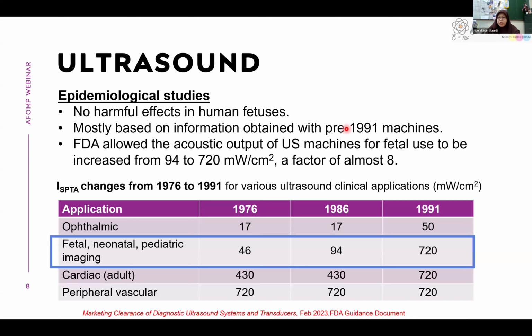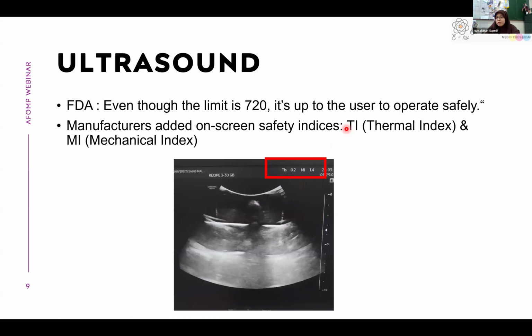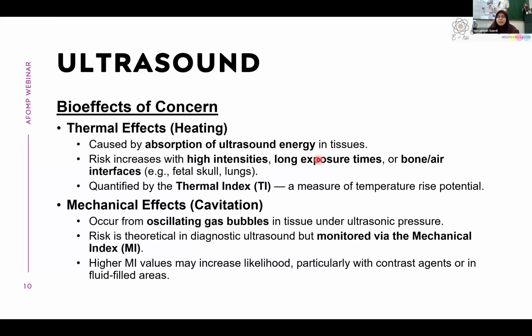But the main reason for this huge jump is that more sophisticated ultrasound machines have been developed, and especially that we now have Doppler imaging, which requires more frequencies, and that somehow contributed to the increment. But the FDA says that even though the limit is 720, it's still up to the user to operate them safely. So it's important for you to know the safe limit of usage. And the manufacturers have added safety indices on the screen. I'm not sure if you are aware of it or not, but we have what we call the TI and the MI, the thermal index and the mechanical index, which you can observe to see the values and get to know the safe limit and the guidelines of use.